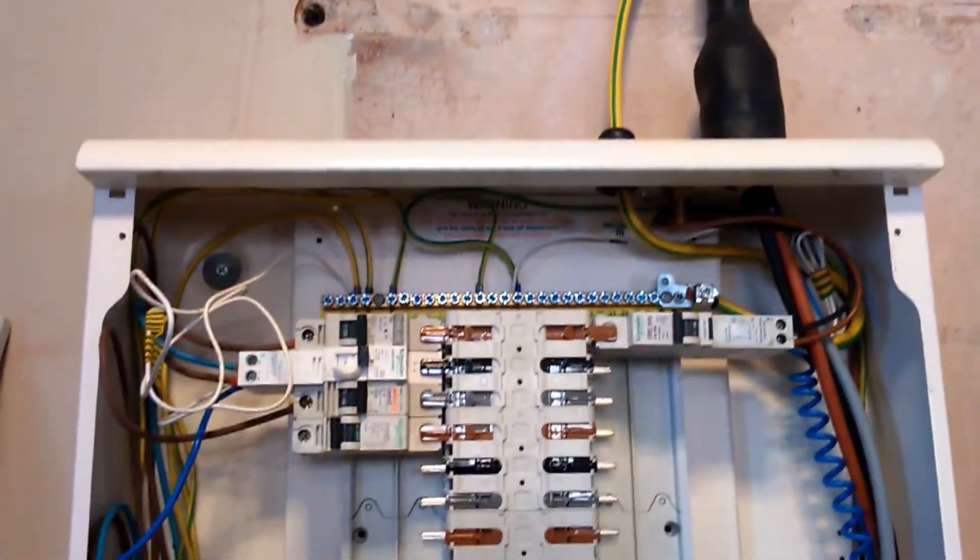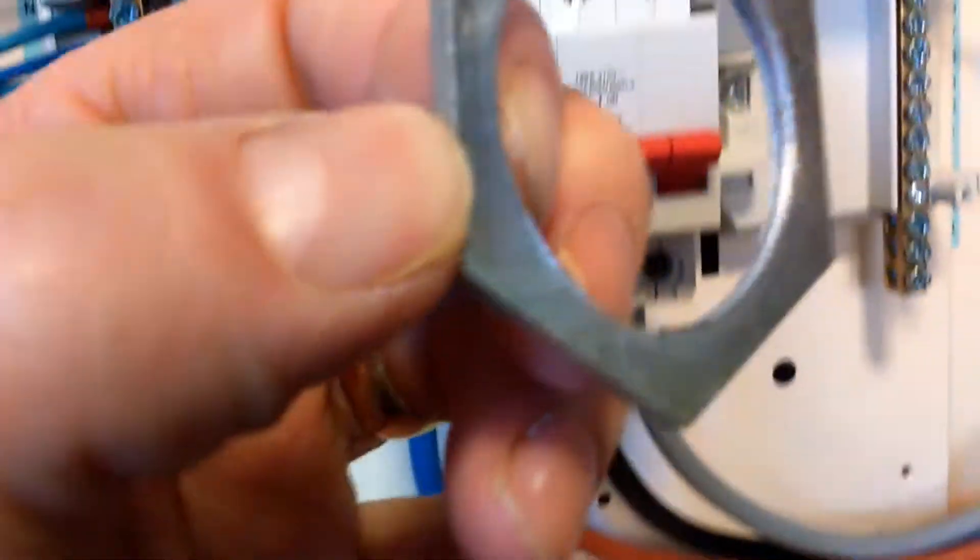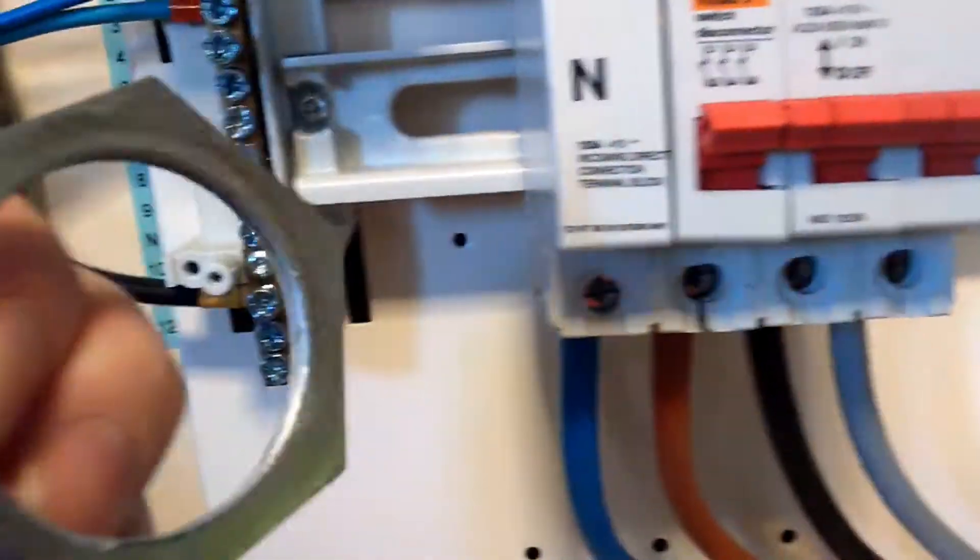Here's a tip for all you young electricians out there: if you're mounting the fuse board on top of trunking and you're going to pass a bush through, please put a lock nut or a lock ring in between the fuse board and the trunking so that you can get your lid of your trunking back on without having to hammer it in.